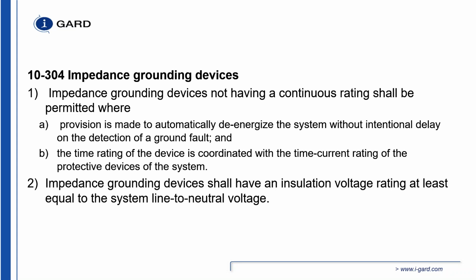So the way we do that, 10-304 basically has the same type of requirements, but for a low resistance grounded system. And for a low resistance grounded system, where you have a resistor not having a continuous rating, you have to de-energize without any intentional delay. The time rating of the device is coordinated with the time current rating of the protective system, and impedance grounding shall have an insulation voltage of at least equal to the system line to neutral voltage.